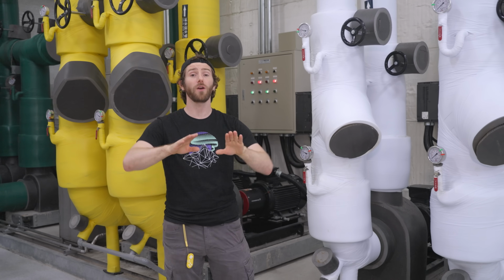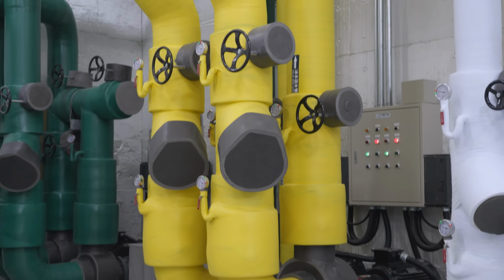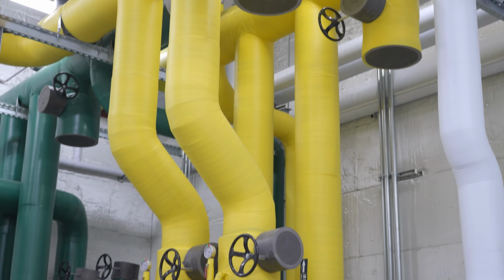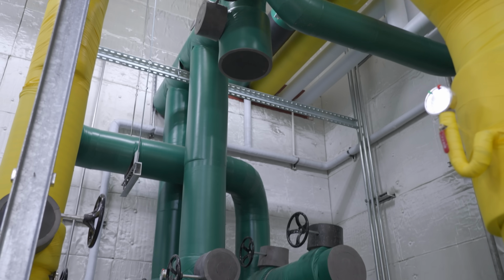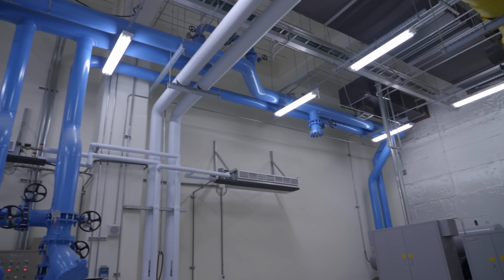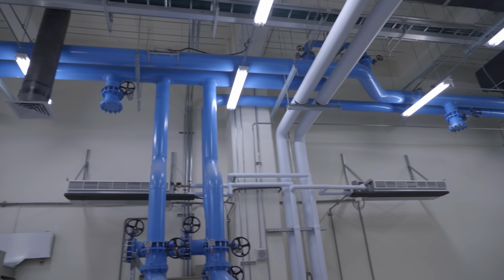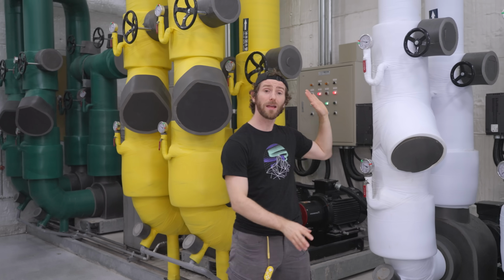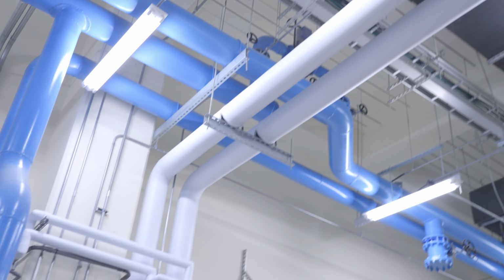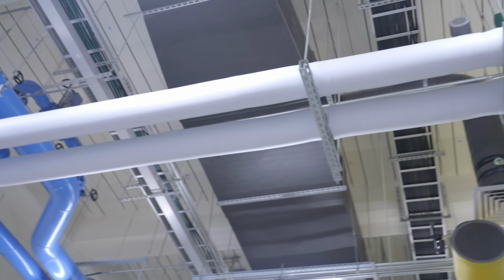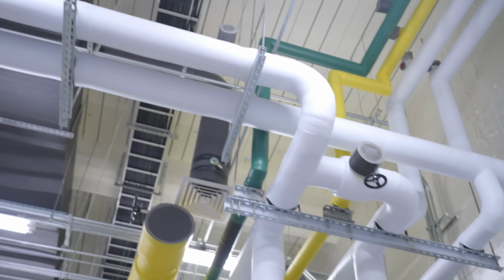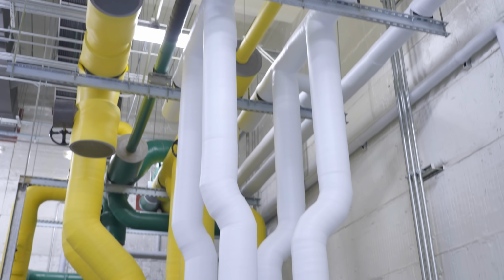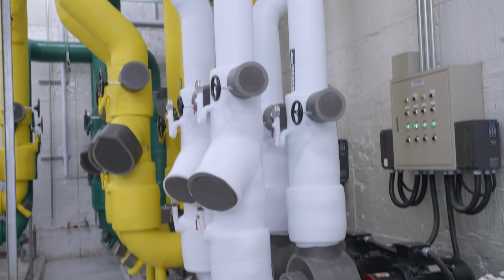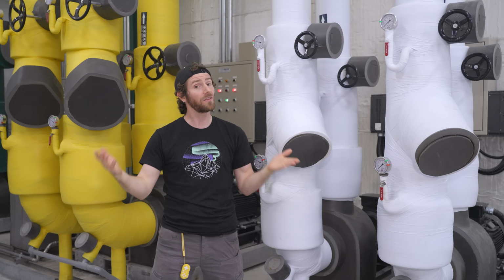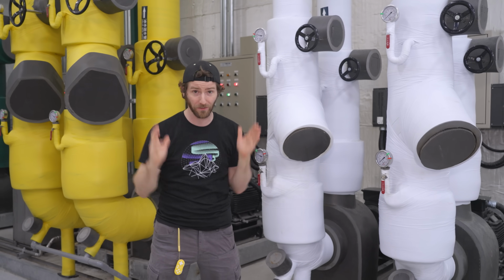The piping in here is all color-coded. Yellow is the cold-ish supply to next door, green is the warm return, blue is the R134A refrigerant that chills the water, and white is actually a building-wide cold supply that runs at 7C and handles chilling the air in the cold aisle next door for any air-cooled deployments. Again, remember, this setup is all about flexibility.